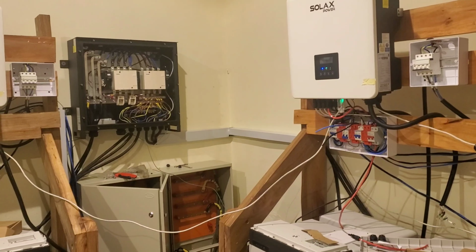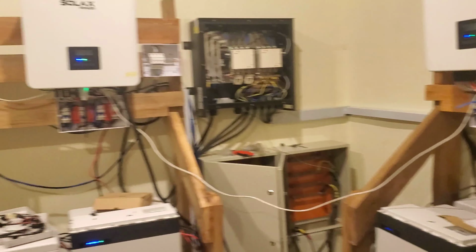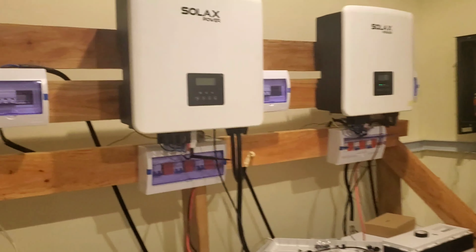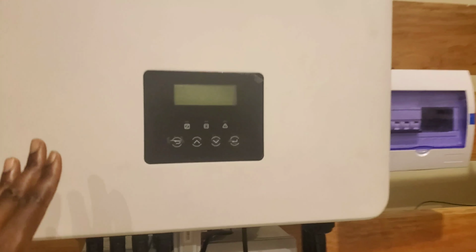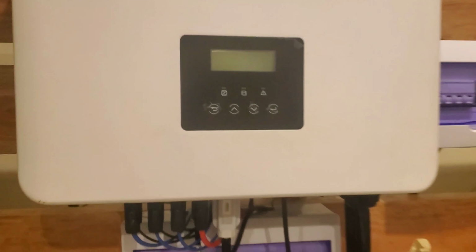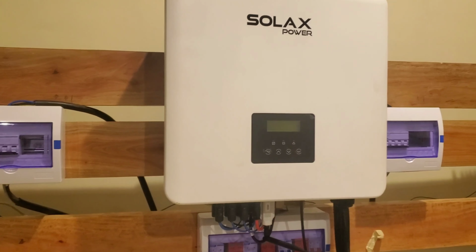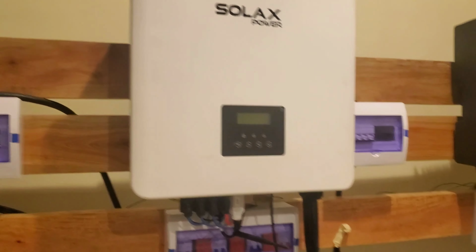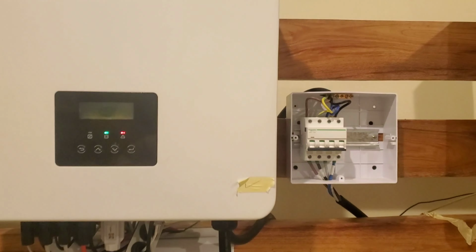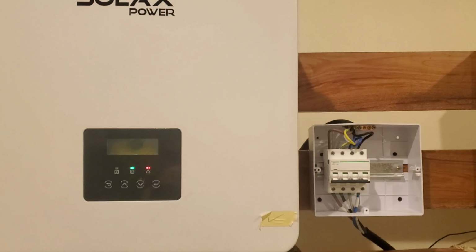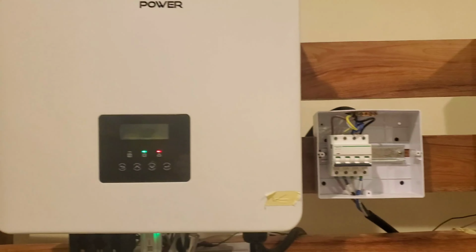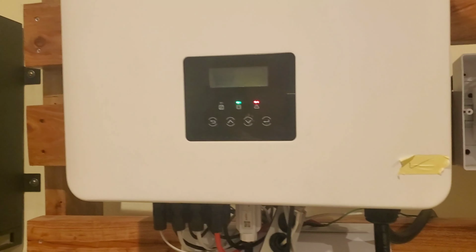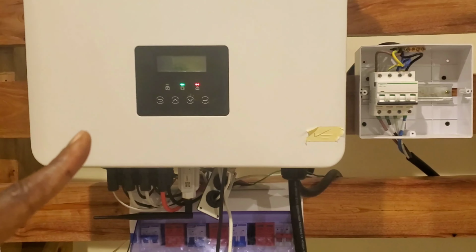So, quick summary. These are how many? 6 times 15? 90 kilowatts. This side is fine. On this side, however, we have a problem. This inverter is the wrong inverter. This cannot parallel. It wasn't sold for a market. It's sold for strictly off-grid purposes. And then this one, we don't know what his issue is, but he's refusing to communicate. Once we do the settings, everyone else goes into master slave. This one stays in free independent mode.